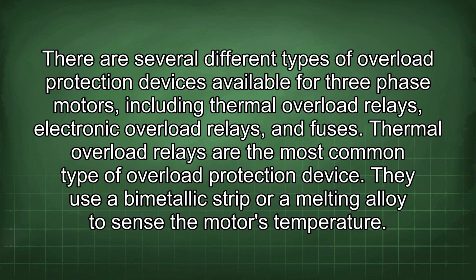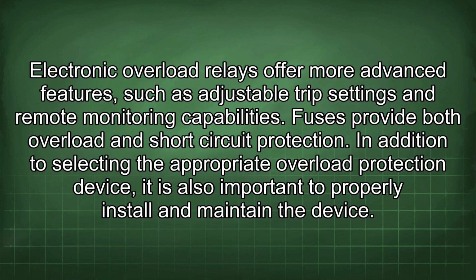There are several different types of overload protection devices available for three-phase motors, including thermal overload relays, electronic overload relays, and fuses. Thermal overload relays are the most common type of overload protection device. They use a bimetallic strip or a melting alloy to sense the motor's temperature. Electronic overload relays offer more advanced features, such as adjustable trip settings and remote monitoring capabilities. Fuses provide both overload and short-circuit protection.